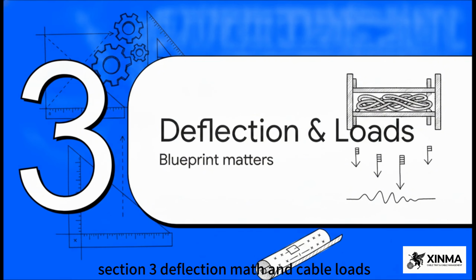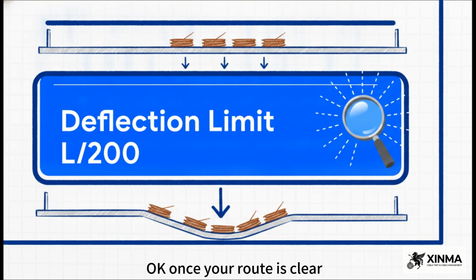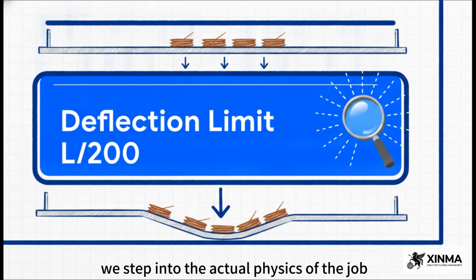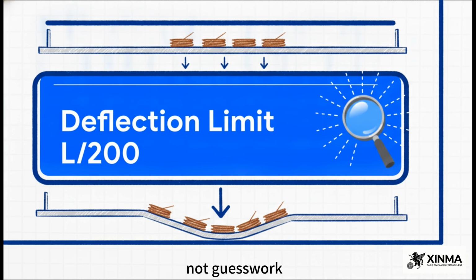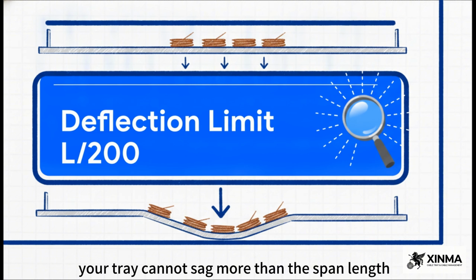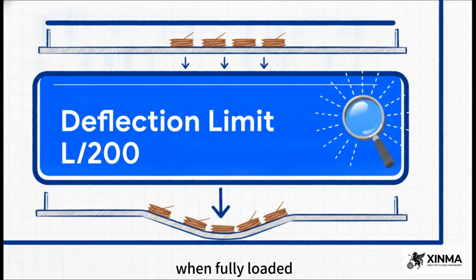Section 3. Deflection math and cable loads. Proving why the blueprint matters. Okay, once your route is clear, we step into the actual physics of the job. At the end of the day, cable trays are at the mercy of hard math, not guesswork. The crucial thing to understand here is the deflection limit, specifically L/200. This is your structural threshold. It essentially means your tray cannot sag more than the span length divided by 200 when fully loaded.